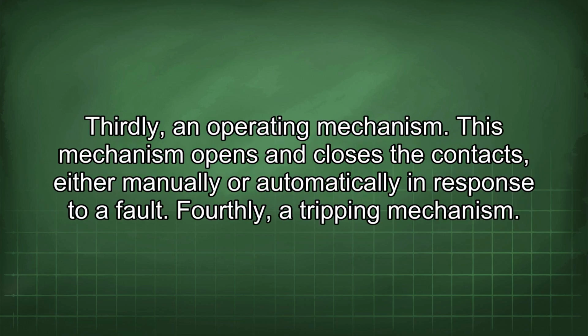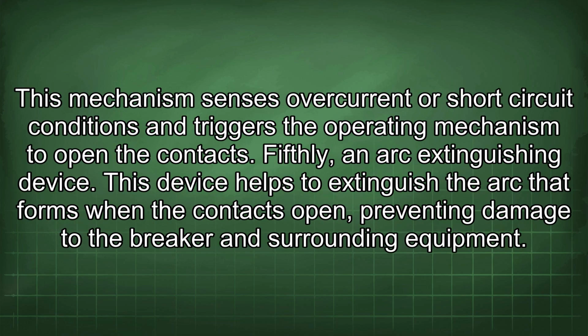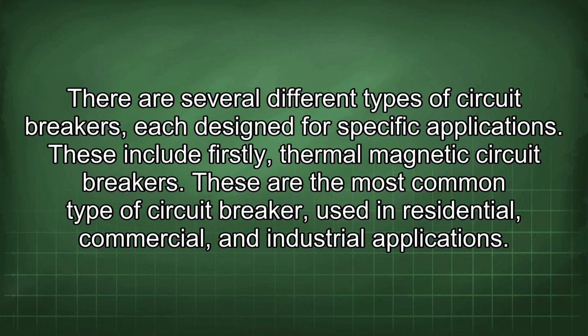Thirdly, an operating mechanism. This mechanism opens and closes the contacts, either manually or automatically in response to a fault. Fourthly, a tripping mechanism. This mechanism senses overcurrent or short circuit conditions and triggers the operating mechanism to open the contacts. Fifthly, an arc extinguishing device. This device helps to extinguish the arc that forms when the contacts open, preventing damage to the breaker and surrounding equipment. There are several different types of circuit breakers, each designed for specific applications.